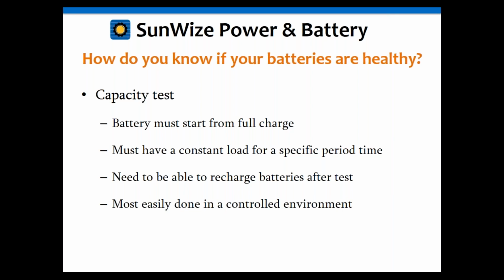The other problem with this is, again, when you've done this, you drain the battery down and then it has to be recharged. So again, this is not something you want to do on a standalone system because first off, it's difficult to get a fully charged battery because it's being cycled constantly. And then after that, you have to recharge it again. So again, this is not easy to do with the system in the field on a standalone one. Again, if you've got a generator there, then you can use that to charge your batteries at the beginning of the test and at the end of the test. If you've got a UPS system, again, it's the same thing, just turn it back on.